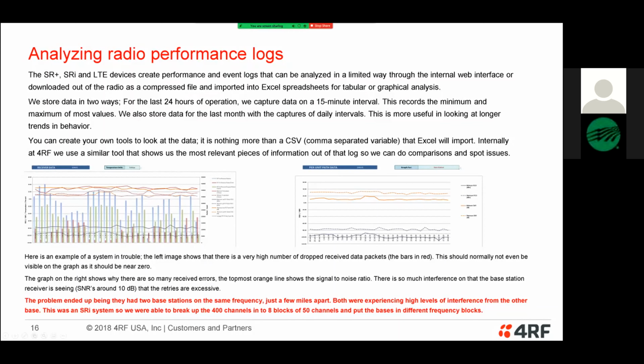And they're showing us things that are pretty relevant for the way this system was behaving. This is actually a real customer, another one in Louisiana, that was experiencing a problem. The big issue was that they were losing a tremendous amount of data. On the left graph, it's the red bars, and that's packets that were not received by the base station. That's horrendous, because normally we should never see lost packets. It'll be down there at less than 1%. But these numbers were so high, in some cases upwards of 20, 30% packet loss.